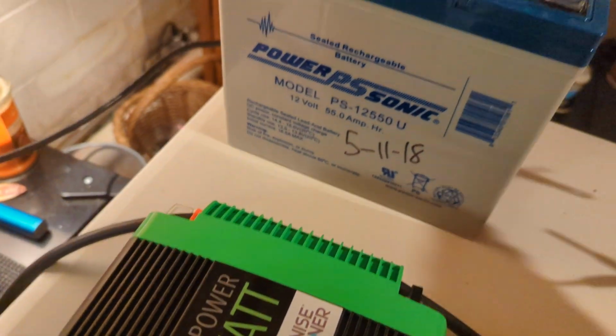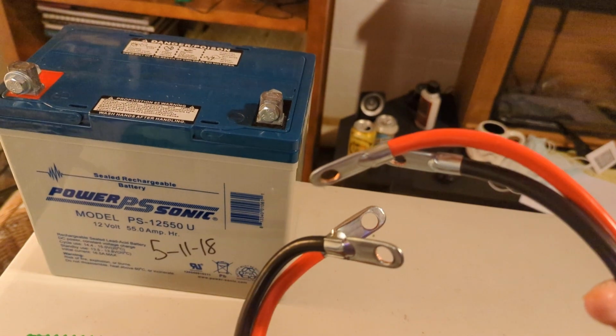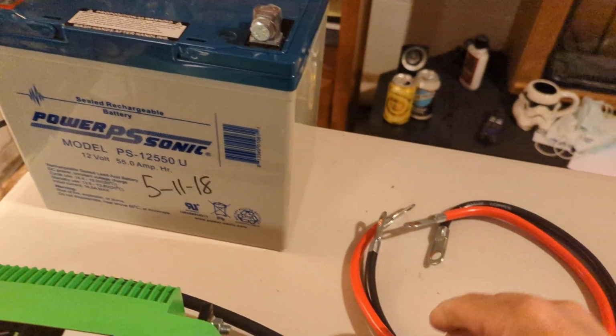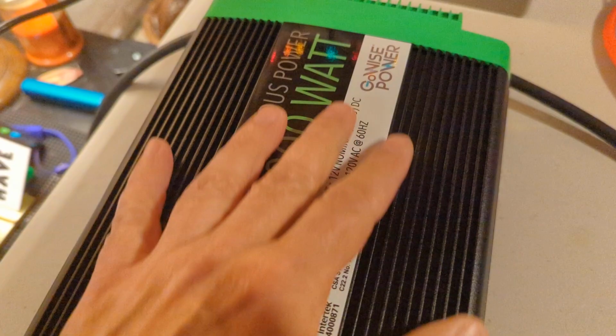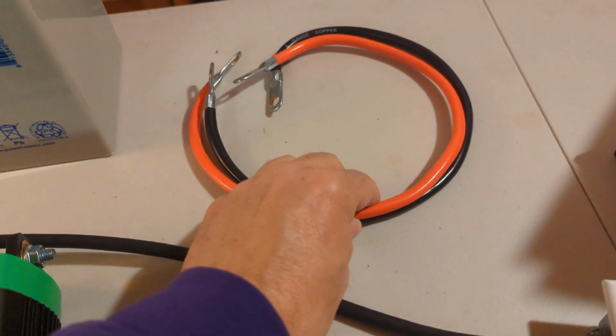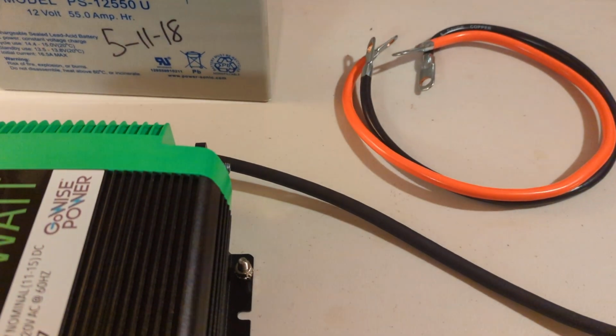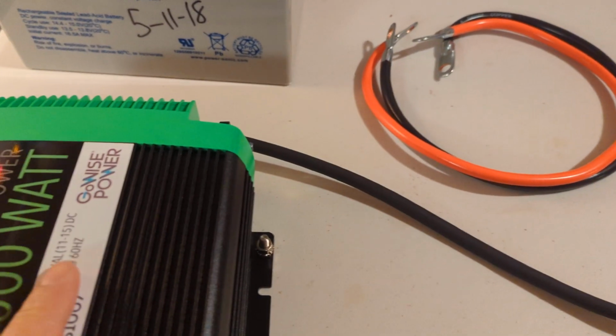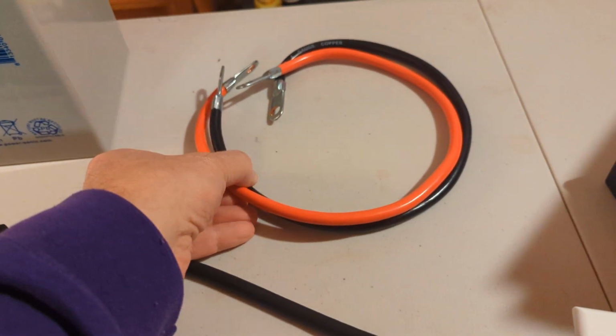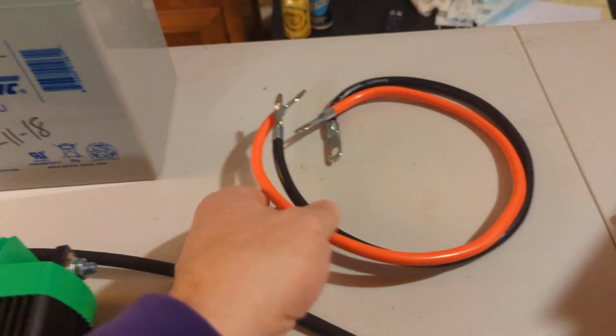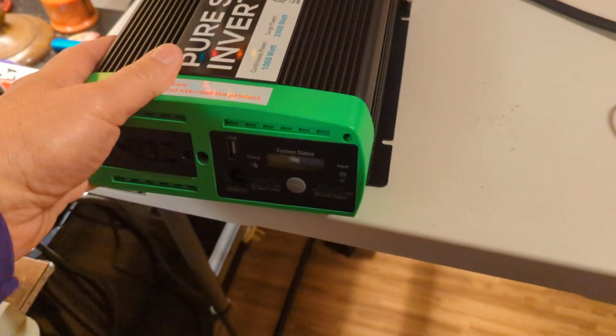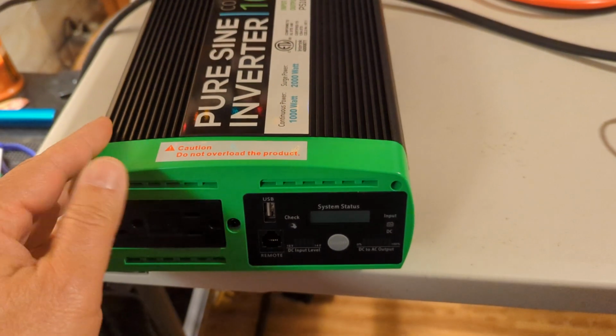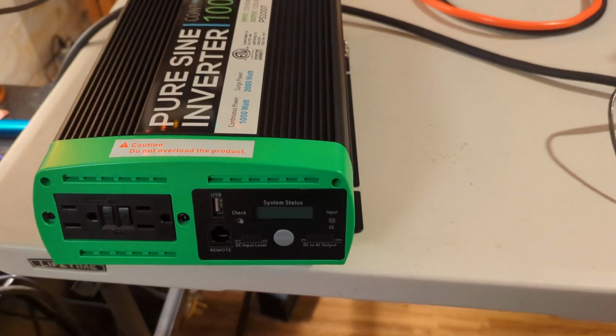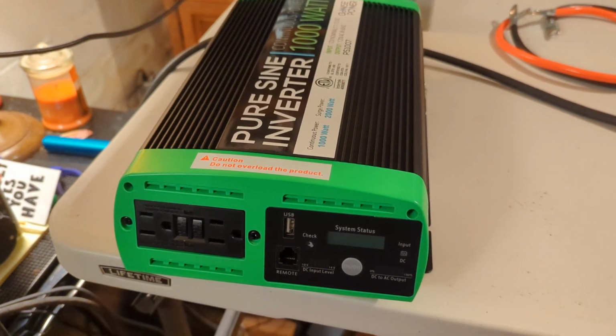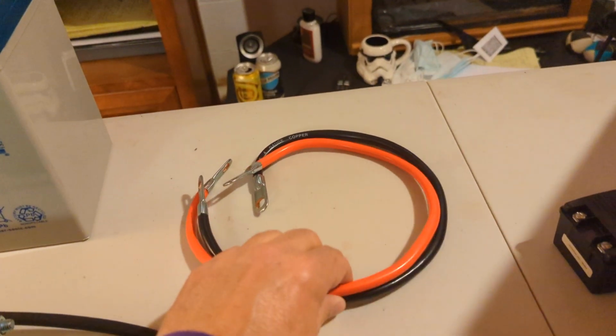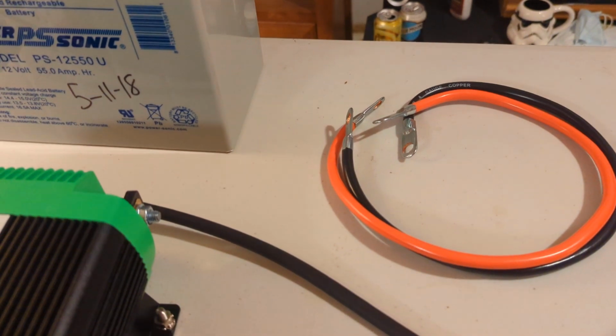So I have a set of 4-gauge cable to hook up. I'm not going to pull anywhere near 1,000 or 2,000 watts in testing, so this cable will be sufficient. If I were doing closer to rated loads, I'd probably use number 2 copper to connect to the storage battery, but for our testing purposes, since we're not throwing a huge load on it, this gauge should be sufficient.